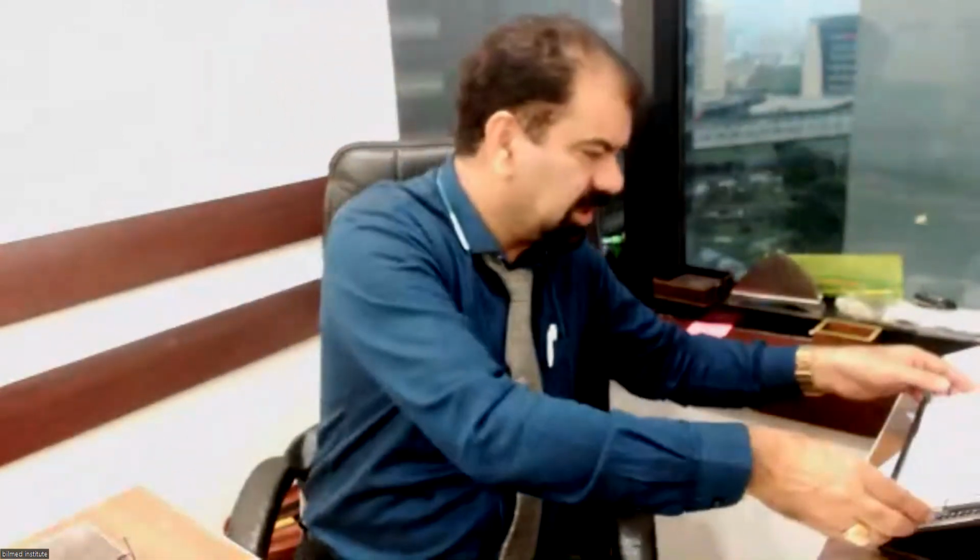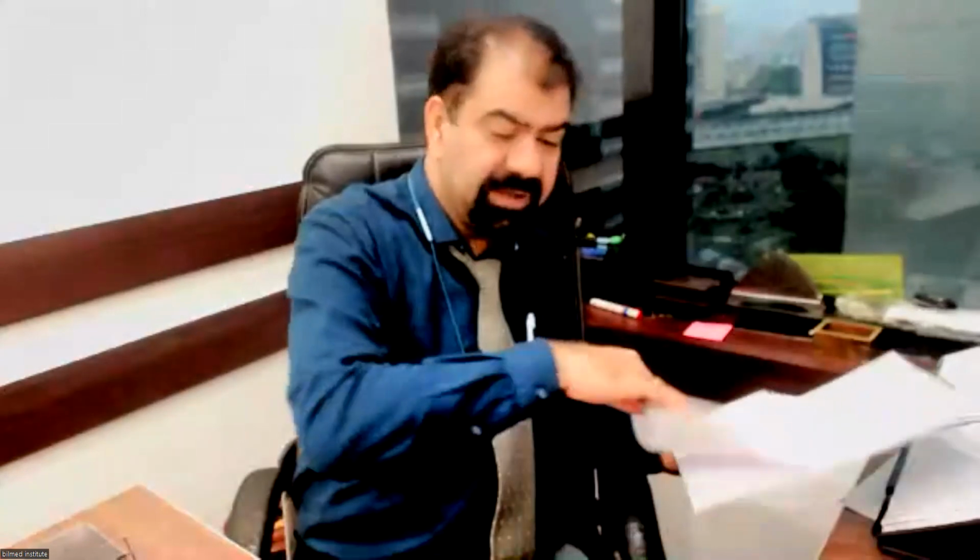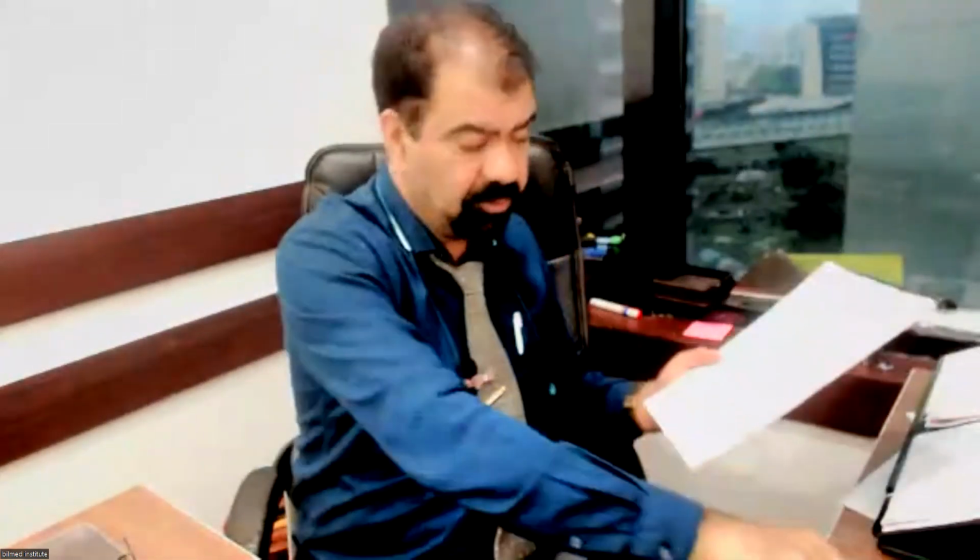Now, Dr. Padam Sagar is posting the question: the role of the TGCs. We have discussed this in the practical sessions of physics and machine settings. We have an overall gain, which will increase or decrease the gain of the overall screen.